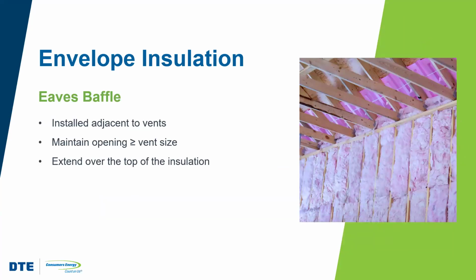Now, whenever air permeable insulation is installed in vented attics, a baffle also has to be installed. The dark pink at the underside of the roof sheathing in this image here is a good representation of an eaves baffle. Now, the baffle's purpose is twofold. First, it directs air through the vents, up and over the insulation. Second, it helps to ensure proper ventilation by preventing the insulation from falling back and blocking the vents. Now, it can be made of any solid material that you like, as long as it's adjacent to the soffit and eave vents and maintains an open area at least the size of the vent.